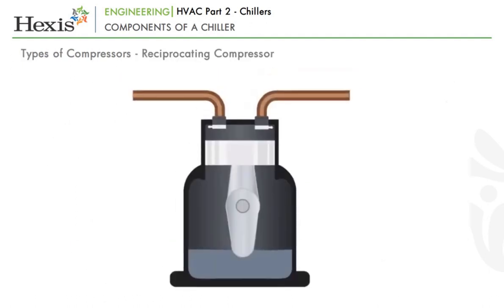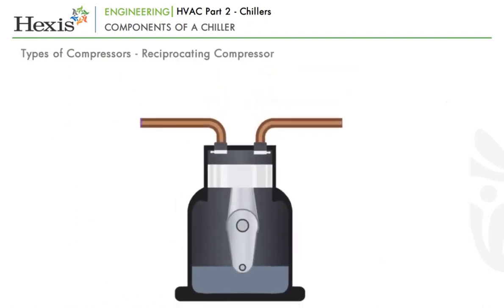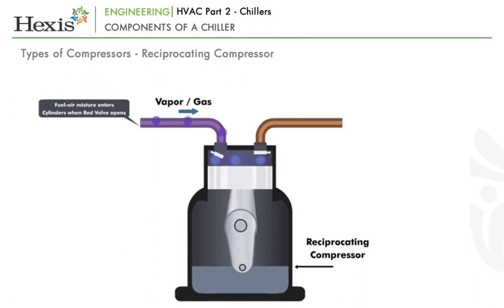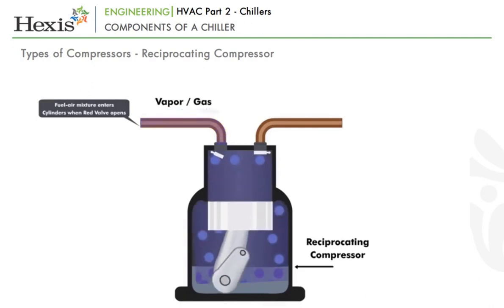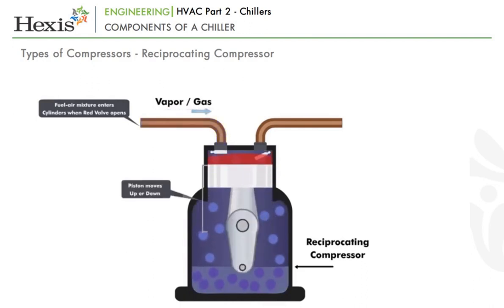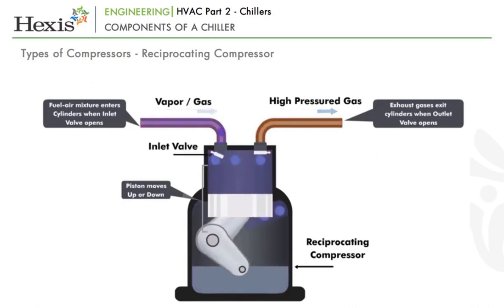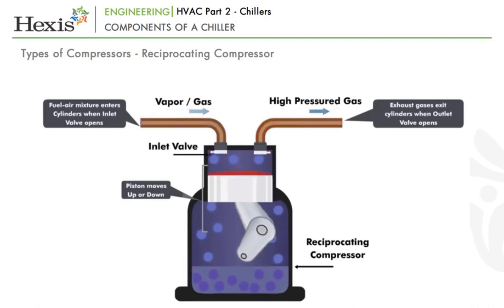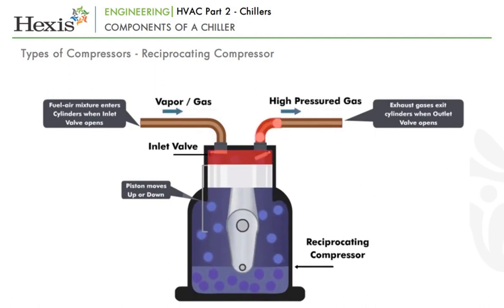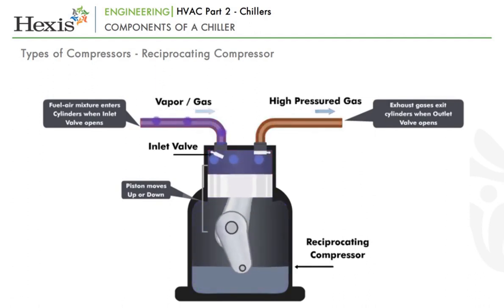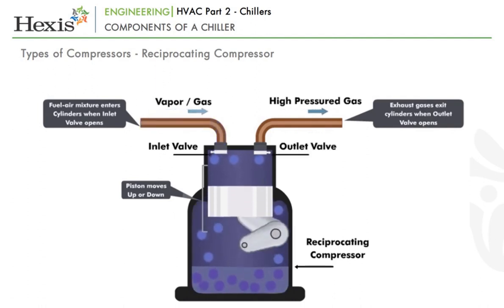The first type of compressor is the reciprocating compressor, which uses pistons moving back and forth to compress the gas much like an engine. It draws in the gas through an inlet valve while moving outwards, and then compresses it during the inward motion, releasing the high-pressure gas through an outlet valve.